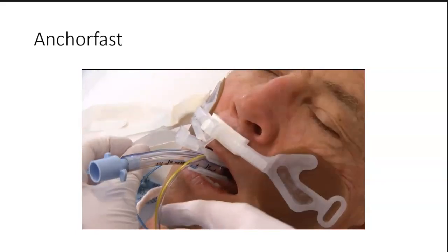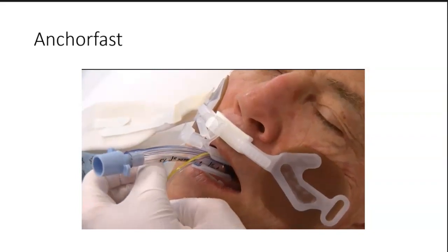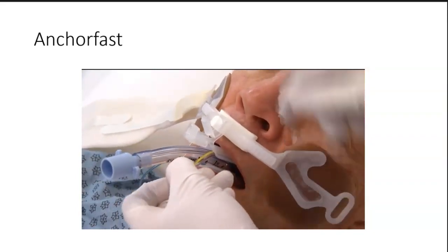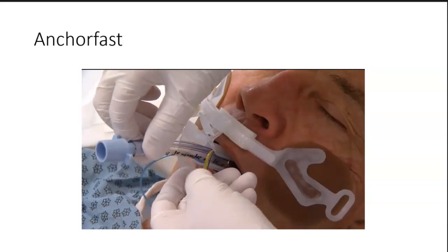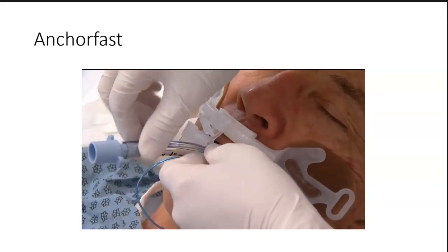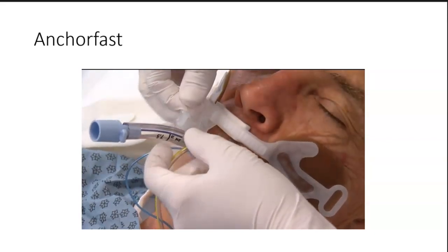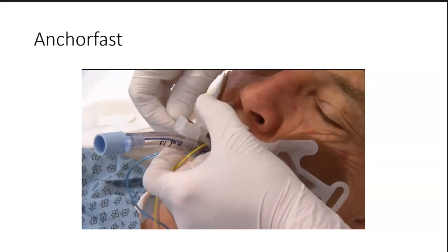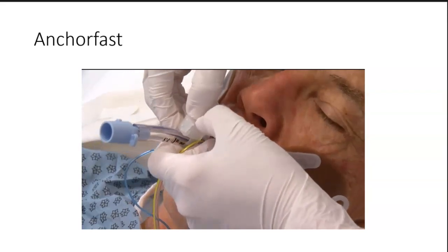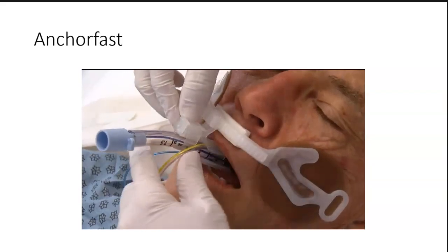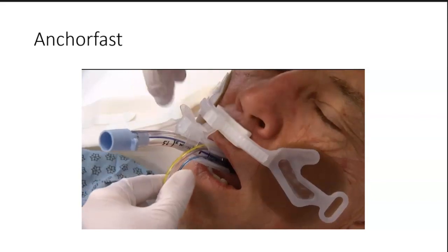Care should be taken to avoid including the cuff inflation tube and the integrated subglottic suction lumen, if present, within the wrap and/or directly under the non-slip grippers when securing the ET tube. Loop the wrap tightly around only the ET tube and pull the remaining portion of the wrap through the security clamp. Secure the wrap by snapping shut the one-click security clamp. An audible click will be heard.